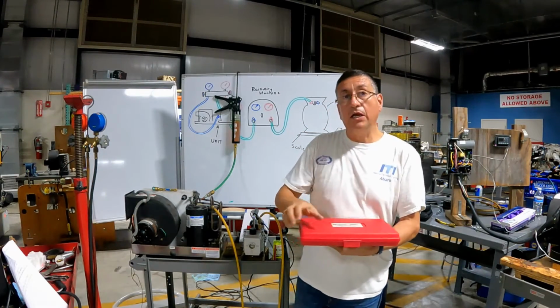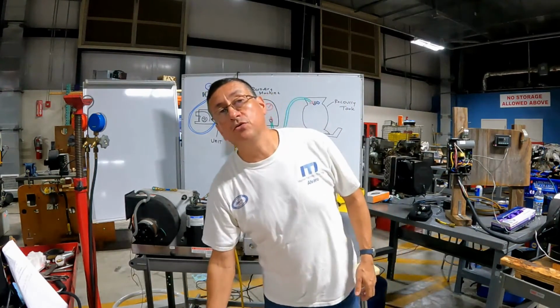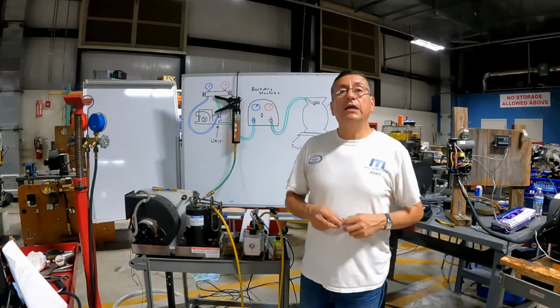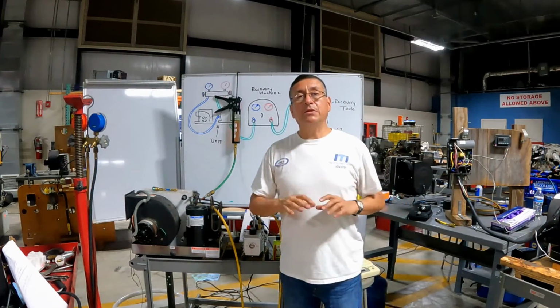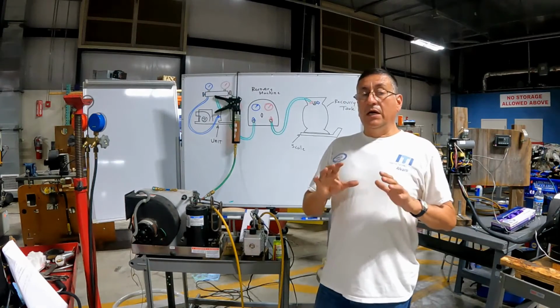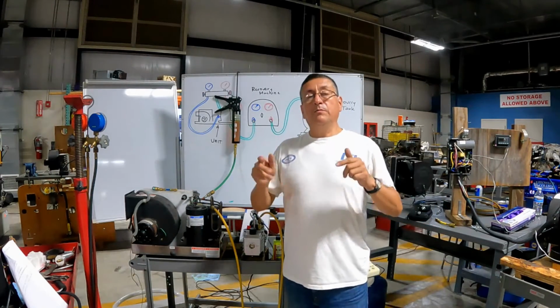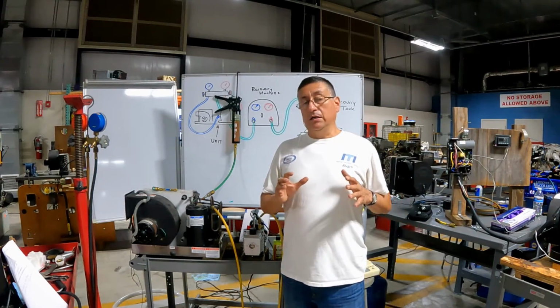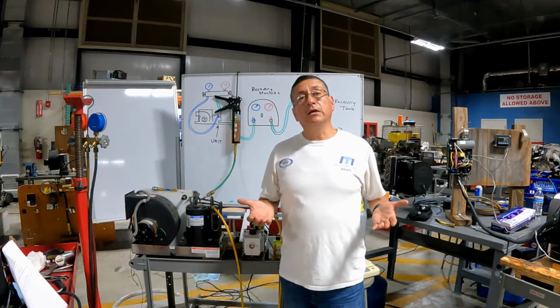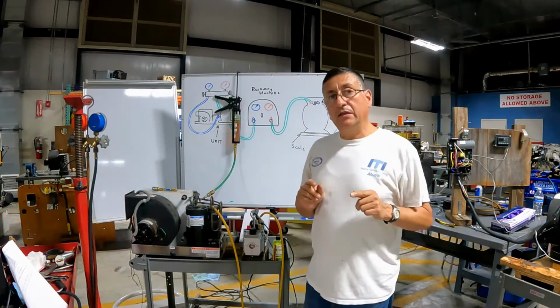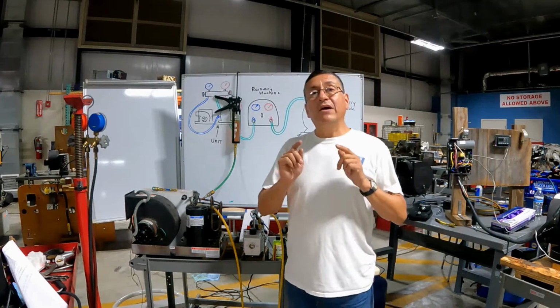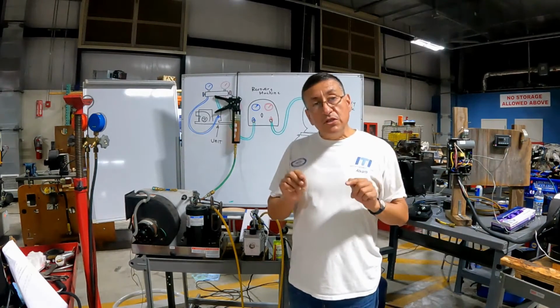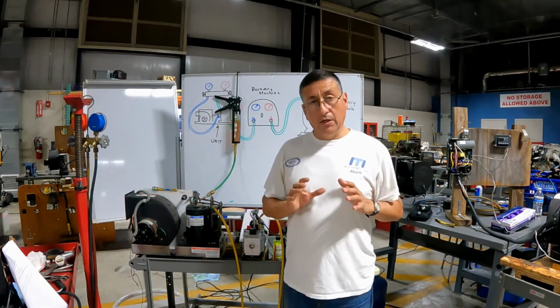Normally the lines are in copper. The majority of the equipment uses copper lines. You cut the line, you do the flares, you install the adapter, and you fix the problem. As soon as you replace the part, you replace the equipment, and you are ready to put back the refrigerant. Before you put back the refrigerant, you need to do the vacuum on the system. You need to purge the system and vacuum the system.